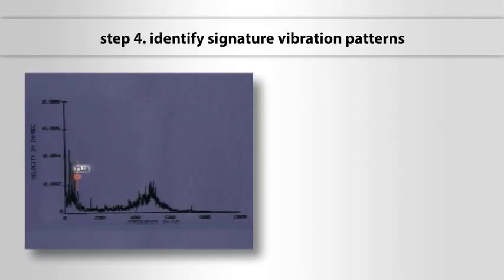Step 4: Identify signature vibration patterns. The signature vibration we're looking for is the vane pass at 73.18 Hz. There are several significant peaks to the right of the one-times, and with a little searching, we can find an exact match at 73.18 Hz.